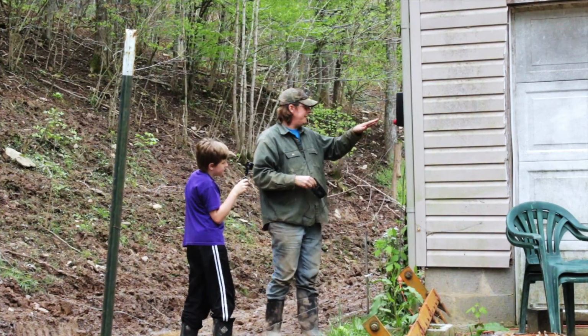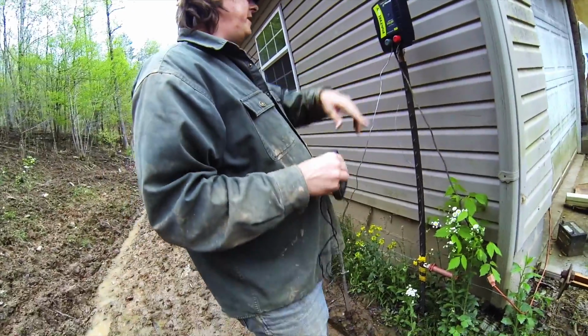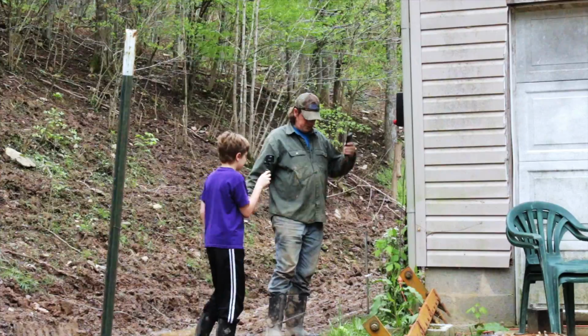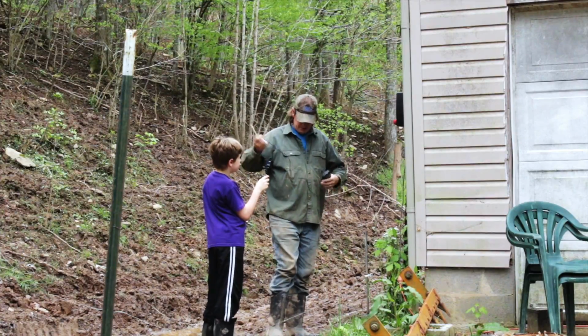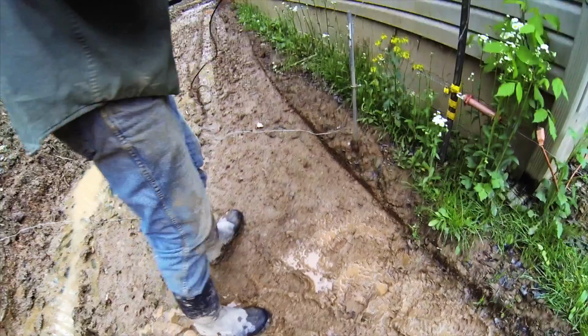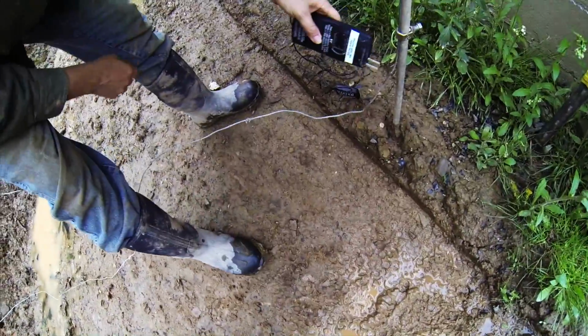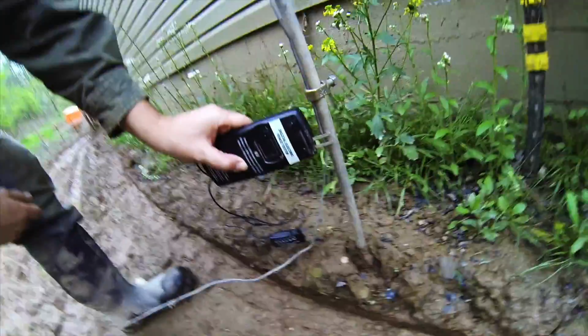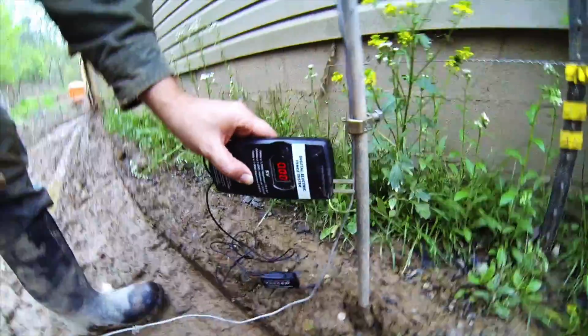Okay, so I've put it back together, put my ground lead back on and my hot back on. So what I'm going to do is test the ground. Instead of putting the tester on the hot, I'm going to put the ground rod in the ground, and put my tester on the ground wire, and see what we get.